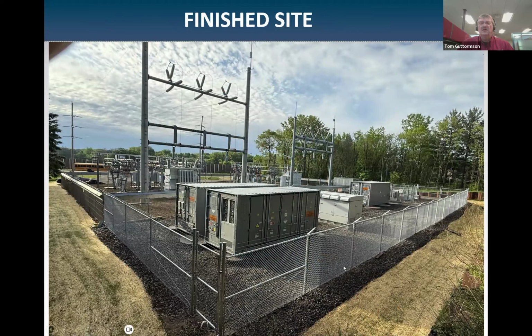So this is the westerly side of the battery yard. Here's the westerly side of the existing substation yard, and you can see that's all contained. Here's BESS 1 and 2, there's BESS 3 over there, with room for a fourth one right down there. In the middle is a container for the step-up transformer and all the inverters. Then on the south side, way over here, you can't see it, but there's a station auxiliary power transformer for all the station aux load and SCADA communications cabinet and all that type of thing. So that's the finished site.